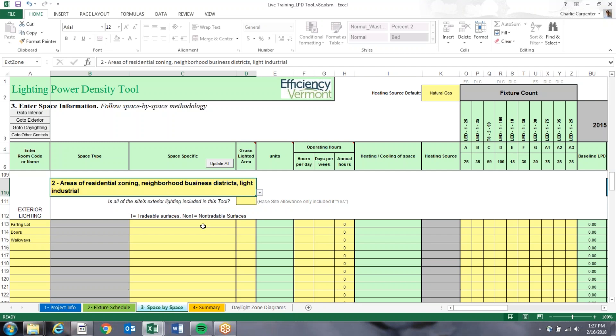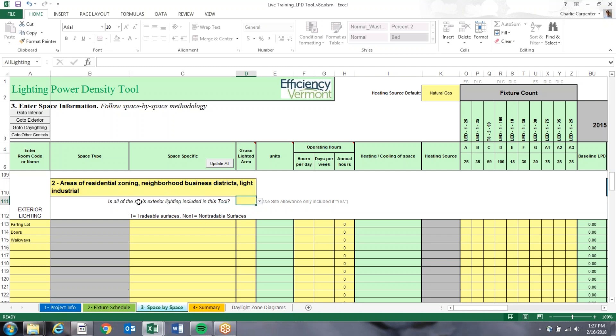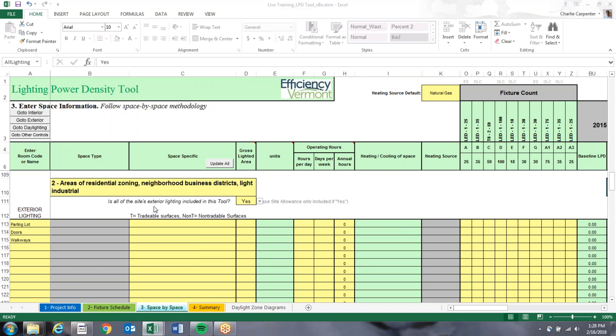There is also a cell asking if all of the site's exterior lighting is included in this tool. If only some exterior lighting is included, select no; if all exterior lights are included, select yes. There's a little extra base site allowance — either 500, 600, or 750 watts — additionally allowed for exterior lighting that will be split evenly between all exterior spaces.